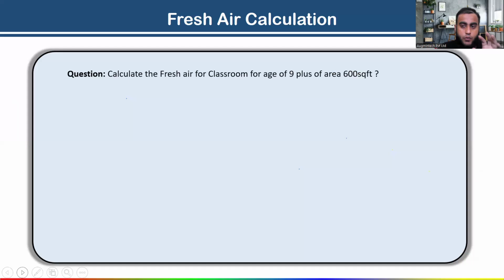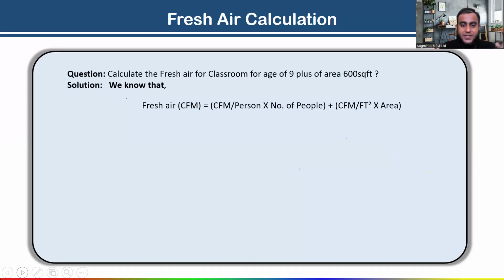Let's say one question is given. We have to calculate the fresh air for a classroom. Inside the classroom, suppose there are 9-year-old students, and the area of that classroom is 600 square feet. If you want to calculate the fresh air CFM for this classroom, how much fresh air do we need to supply? We have a formula, as I told you: CFM per person into number of people, plus CFM per square feet into area.